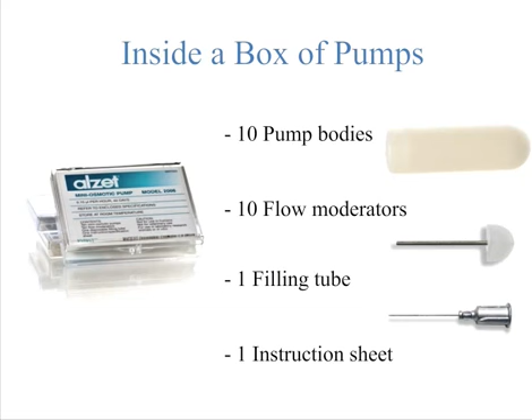Now, it is imperative that you review this instruction sheet because it contains detailed steps on preparing the pump. Also, the instruction sheet contains lot-specific data that may differ from our marketing materials. And here's a good example of what I mean. This is actual lot data from one of our 2002 pumps. Now, in our marketing materials, we say that 2002 is a 200 microliter size pump and infuses at 0.50 microliters per hour. Now, when we manufacture these pumps, we try to get as close to these values as possible, but there will inevitably be some variations.